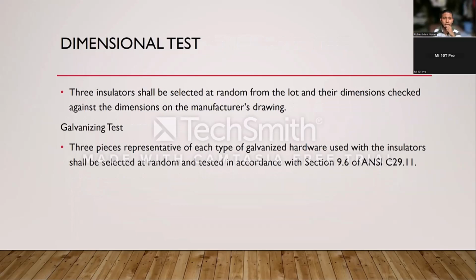The dimensional test. 3 insulators shall be selected at random from the lot to check against the dimensions of the manufacturer's drawing. The galvanizing test, 3 pieces representative of each type of galvanized hardware used with the insulator shall be selected in accordance with section 9.6 of ANSI C29.11.